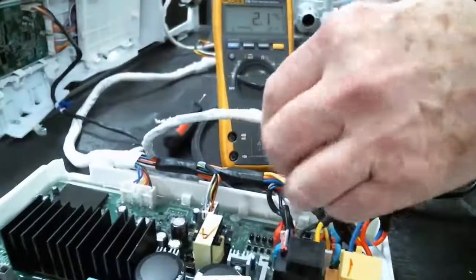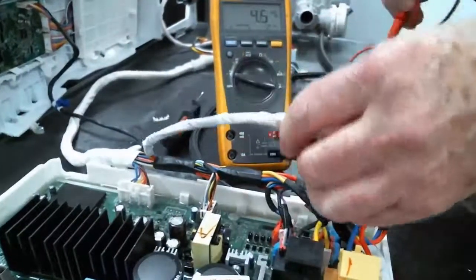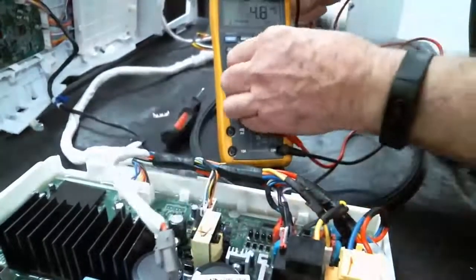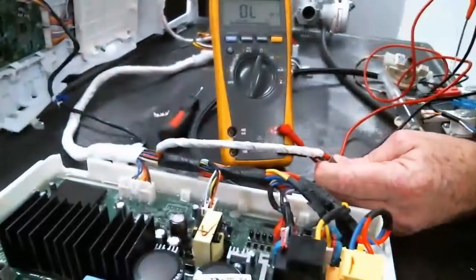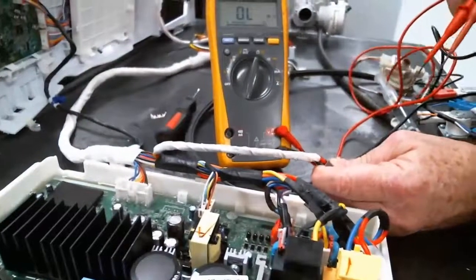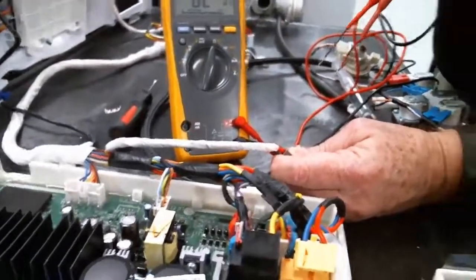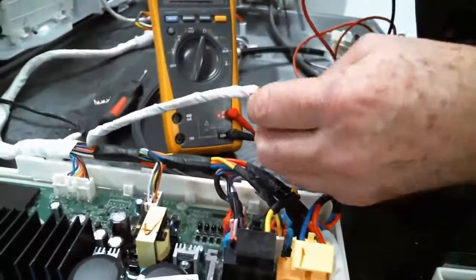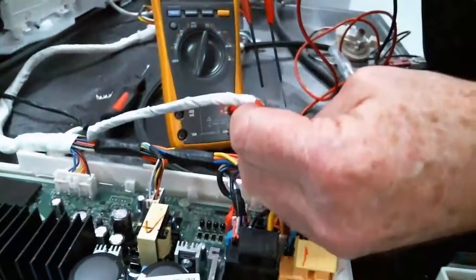Now all I'm going to do is a resistance check, and I'm looking for somewhere from 5 to about 15 ohms. So let's set this for ohms and choose any two colors. You're going to do all three combinations: red to blue, blue to yellow, and red to yellow. They should be pretty consistent when you're checking the three windings.